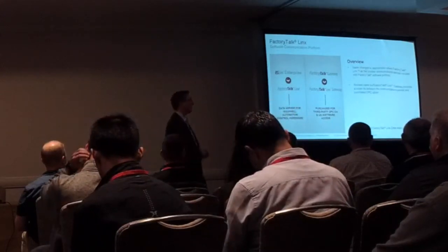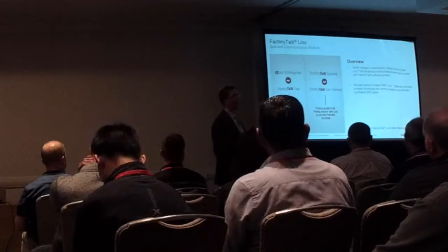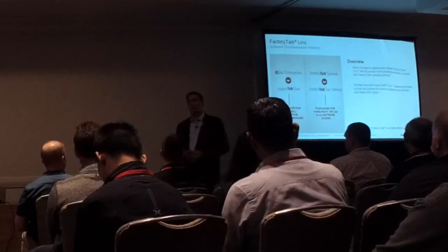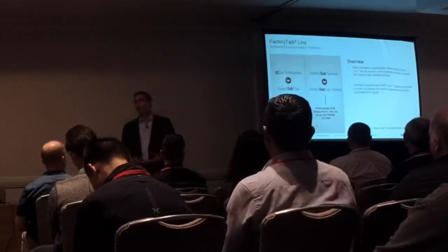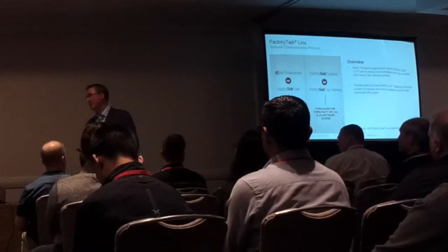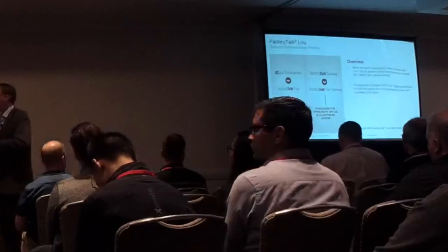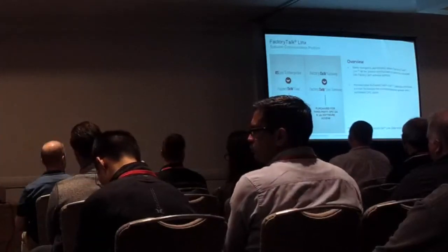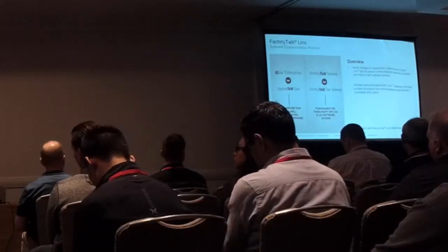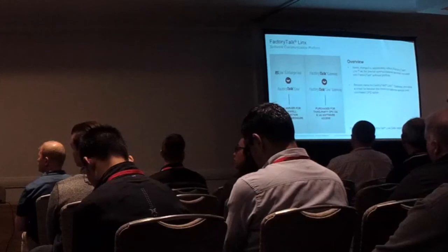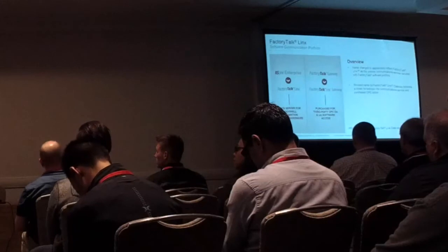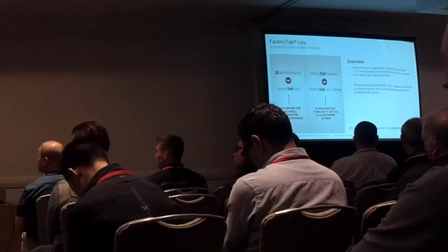Now, an important part of this addition is we've introduced OPC UA capability into FactoryTalk Linx, starting in this most current release. When you install Rockwell products, and you by nature install FactoryTalk Linx, you will have OPC UA client capabilities just native as part of the system. What that means by just using Rockwell FactoryTalk products is you'll now have the ability to go out and grab data from third-party OPC UA servers and bring it into that architecture. That's just naturally part of what you have with that product.